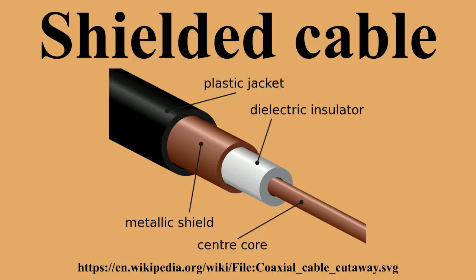In circuits over 2000 volts, cables usually have a shield layer of copper or aluminium tape or conducting polymer. If an unshielded insulated cable is in contact with earth or a grounded object, the electrostatic field around the conductor will be concentrated at the contact point, resulting in corona discharge and eventual destruction of the insulation. Leakage current and capacitive current through the insulation presents a danger of electrical shock. The grounded shield equalizes electrical stress around the conductor and diverts any leakage current to ground.